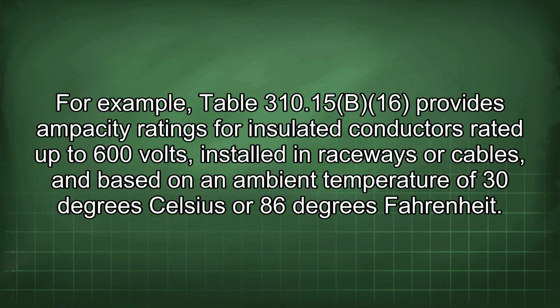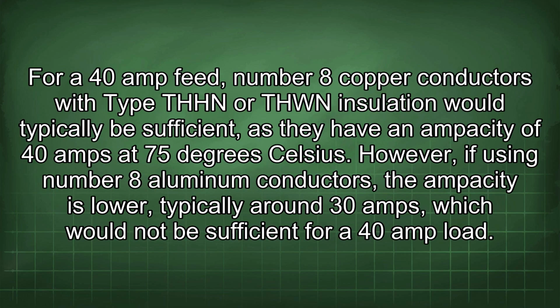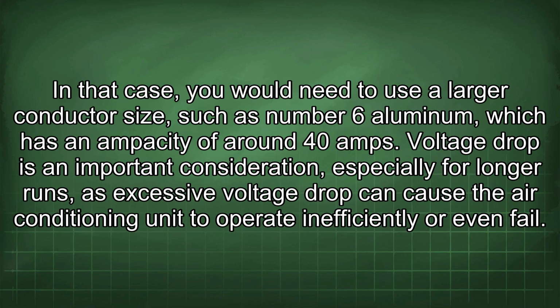For example, Table 310.15(B)(16) provides ampacity ratings for insulated conductors rated up to 600 volts, installed in raceways or cables, and based on an ambient temperature of 30 degrees Celsius or 86 degrees Fahrenheit. For a 40 amp feed, number 8 copper conductors with type THHN or THWN insulation would typically be sufficient, as they have an ampacity of 40 amps at 75 degrees Celsius. However, if using number 8 aluminum conductors, the ampacity is lower, typically around 30 amps, which would not be sufficient for a 40 amp load. In that case, you would need to use a larger conductor size, such as number 6 aluminum, which has an ampacity of around 40 amps.